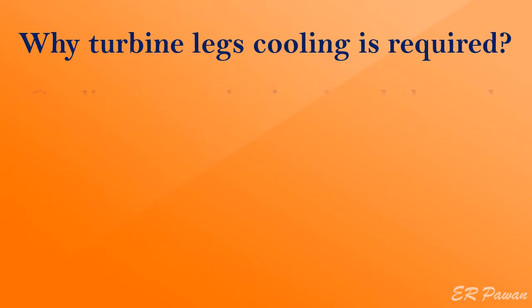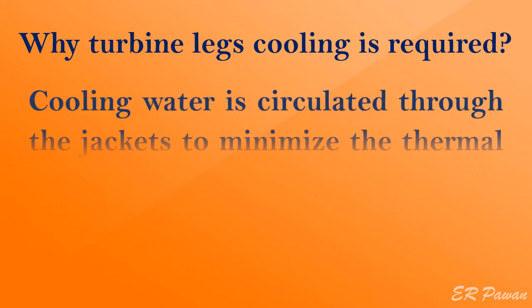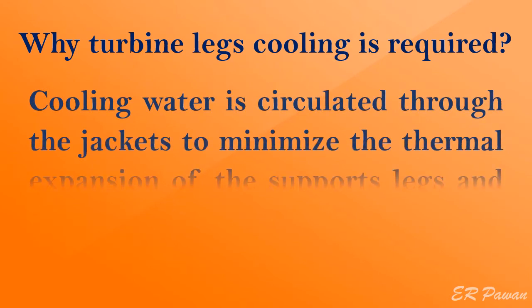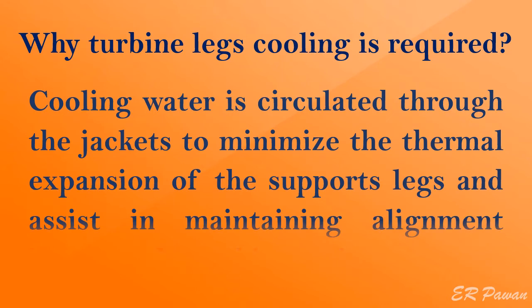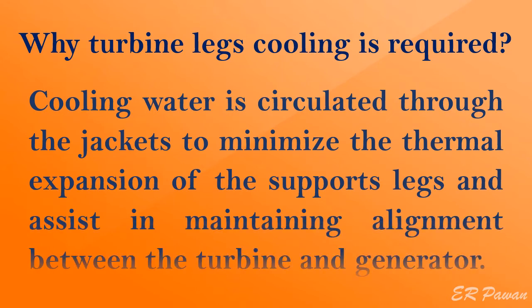Why is turbine legs cooling required? Cooling water is circulated through jackets to minimize the thermal expansion of the support legs and assist in maintaining alignment between the turbine and generator.